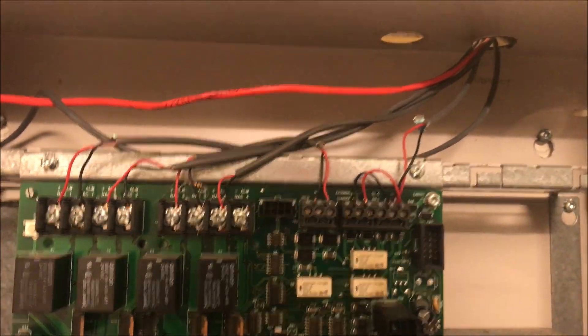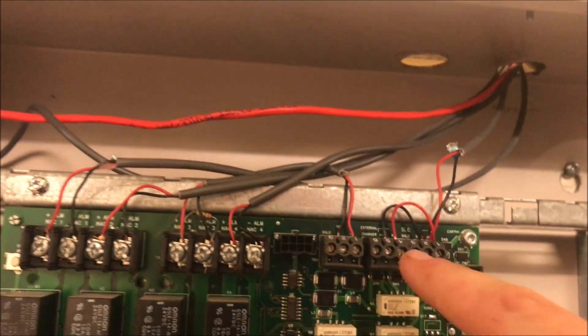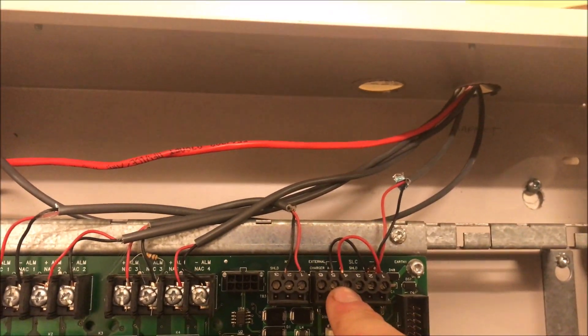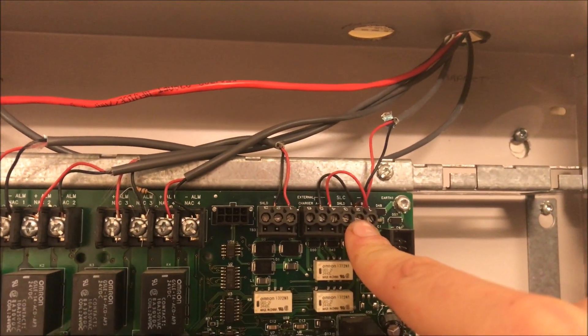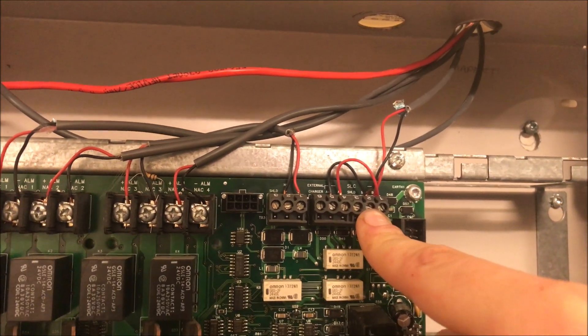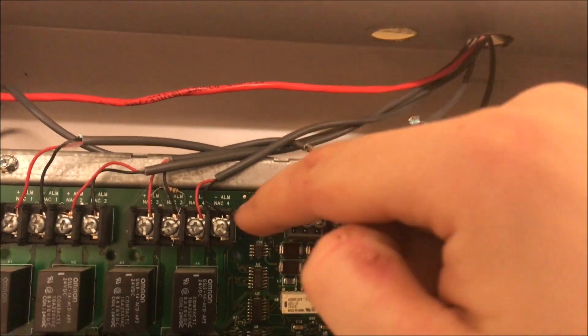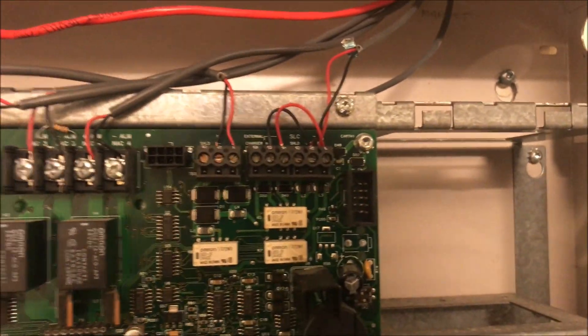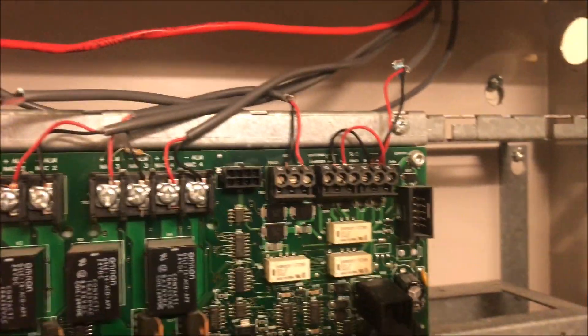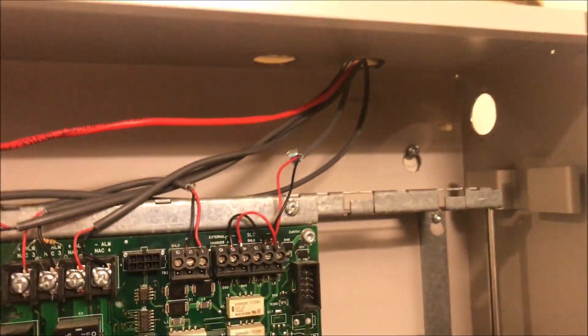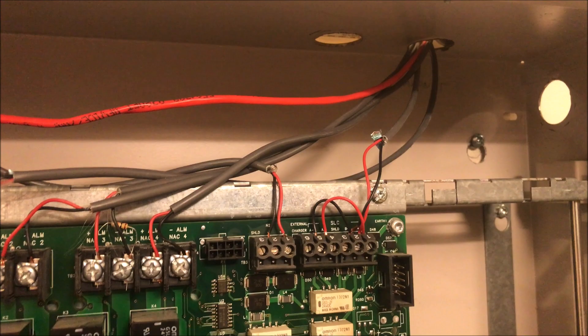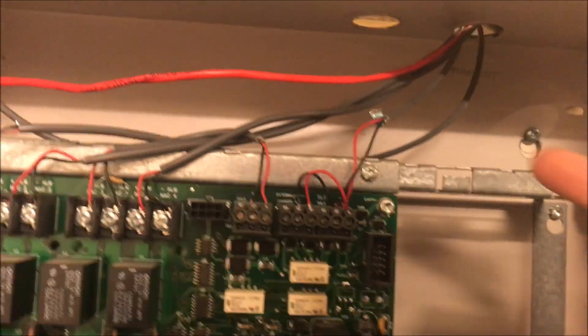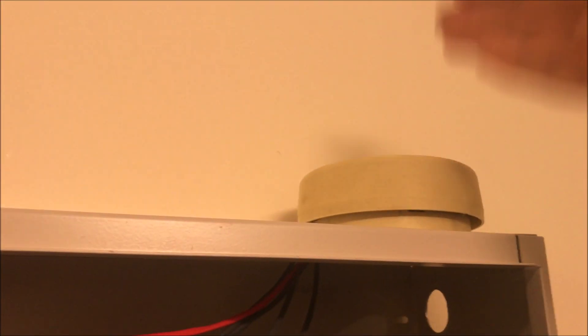Here you have your external charger, then your Class A inputs—positive and negative—then your Class B inputs—positive and negative. If you need to make it Class B when it's set up as Class A, you just jump A and B. These go out to all your IDnet cards. Any of those little modules all come off this wire. It's not like a conventional panel where you need a bunch of wires going to each device or zone. All 11 of my devices come through this single pair of wires, and then they go in the next room.